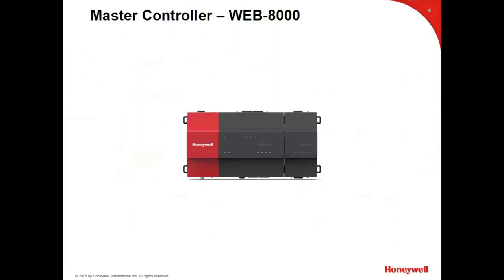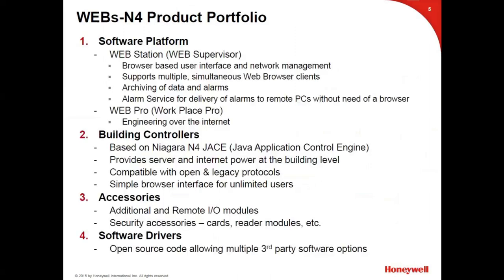First, with the master controller — the Web 8000. If someone is familiar with the Niagara Framework and a JACE, obviously that's what this is. Some highlights: the web station, the web supervisor, is software that sits on your server — a browser-based graphical user interface. That's usually where all end users access their system via username and password. The controllers, which I like to call master controllers or JACEs, are compatible with open and legacy protocols. You can install third-party drivers and connect your field controllers to the network.